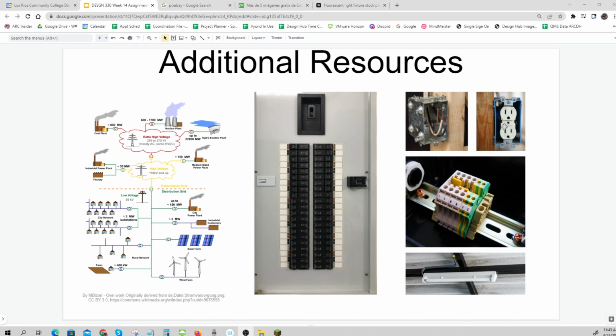Sometimes those get wired in directly in a junction box, and sometimes there's just a receptacle. This is a 110 receptacle. 208 receptacles look a little different, but someone pulls wires from here to the receptacle, wires it up to the plug, puts a cap on it, and then you can plug it in and your power gets there. So that's how our power gets to where we need it to go.